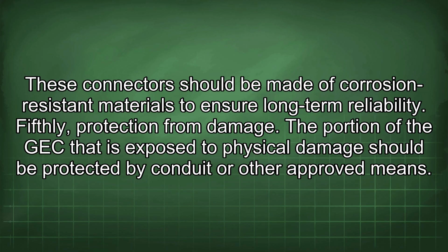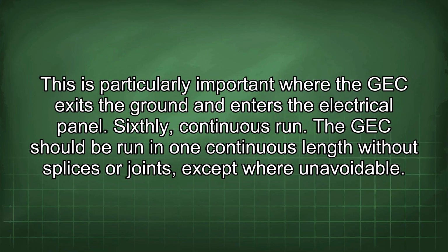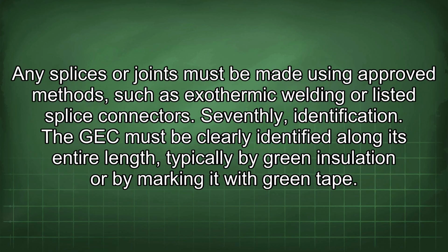Fifthly, protection from damage. The portion of the GEC that is exposed to physical damage should be protected by conduit or other approved means. This is particularly important where the GEC exits the ground and enters the electrical panel. Sixthly, continuous run. The GEC should be run in one continuous length without splices or joints except where unavoidable. Any splices or joints must be made using approved methods such as exothermic welding or listed splice connectors.